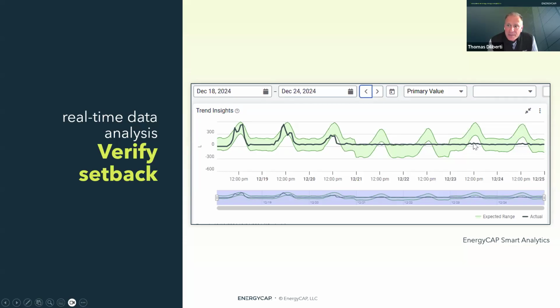I share this because one recommendation is that buildings on your campuses which can be set back should be, with regularity—whether on weekends, or longer periods like holidays between Christmas and New Year's when occupants aren't in the building. This data tells that story, letting you measure and verify that performance, and then quantify the benefits.